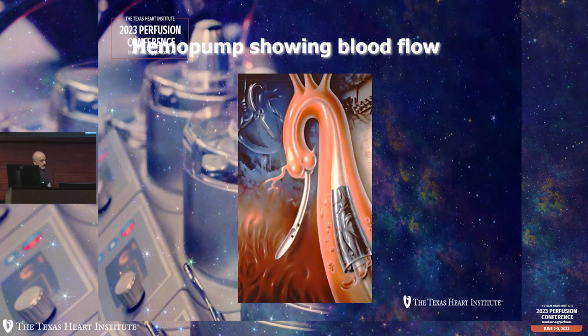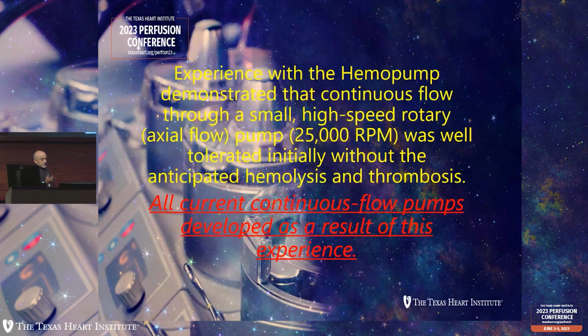The hemopump had a motor outside of the body. The Impella has the motor now embedded in the pump. So experience with the hemopump demonstrated that the continuous flow through a small high-speed rotary axial flow at 25,000 RPM was well tolerated, which was never demonstrated before that day. Everybody thought that 25,000 RPM would be way too detrimental to the RBCs and the blood, and you would not survive. Apparently that wasn't the case. And all current continuous flow pumps developed as a result of this experience, including the centrifugal pumps as well.